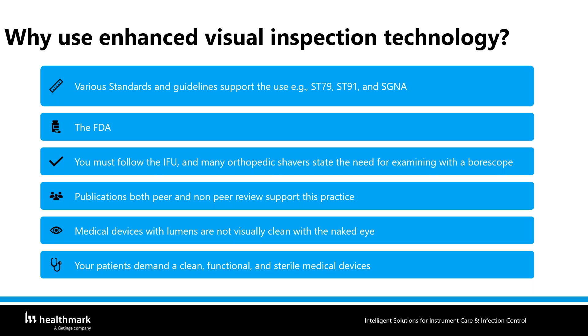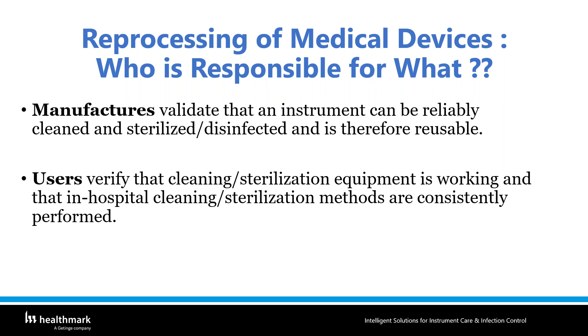On top of that, if the IFU doesn't exist or there's no standard, sometimes a peer-reviewed publication mentions, for example, that a group reviewed these devices and found that you need to do a certain activity for cleaning. And medical devices with lumens are not visibly clean to the naked eye. That's the issue we had with John Harrison's arthroscopic shaver. Our patients demand clean, functional, and sterile medical devices. FDA says manufacturers need to validate that an instrument can be easily cleaned, and the user needs to verify. That verification falls under cleaning and sterilization, and whether it is being performed consistently.